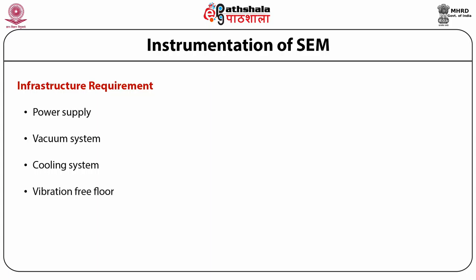The basic components used in the electron optical system are: number one, a source of electrons called the electron gun; number two, lenses; number three, scanning coils; detectors to collect the signals; sample stage; and display or data output devices. The infrastructure requirements are: power supply, vacuum system, cooling system, and vibration-free floor.